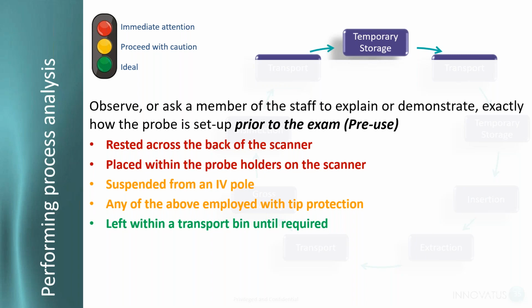So temporary storage. When the probe is brought into the department for temporary storage, rested on the back of the scanner, never a good idea. Placed within the probe holders of the scanner, never a good idea. Those probe holders are not designed for TE probes. They're designed for standard transthoracic probes. The TE probes, because of their length and just the way they're designed, that is a horrible place to store them. Suspended from an IV pole, a little bit better. These probes do come with typically a little ring, so you can do that. Not recommended. Any of the above employed with tip protection, still not recommended, but left within a transport bin with tip protection until required. I should have put that in there. I will add that after this webinar, but left in the transport bin is ideal until required for usage.